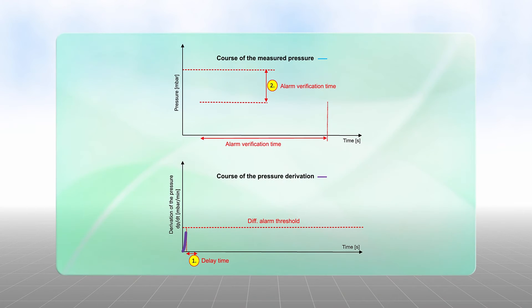Because the rush of air quickly disappears, the measured pressure decreases so that the alarm verification time expires without incident. No fire alarm is triggered.